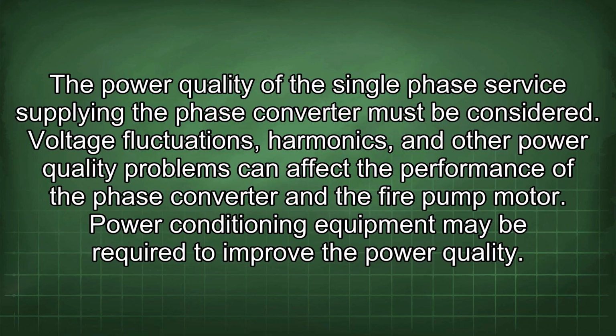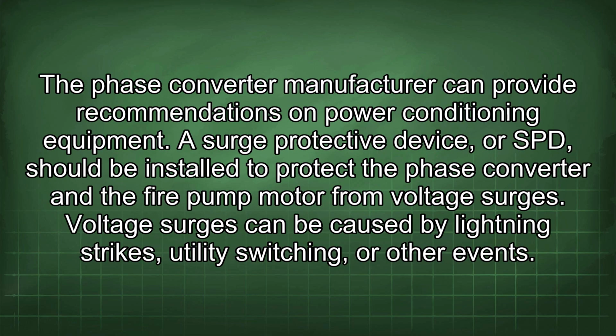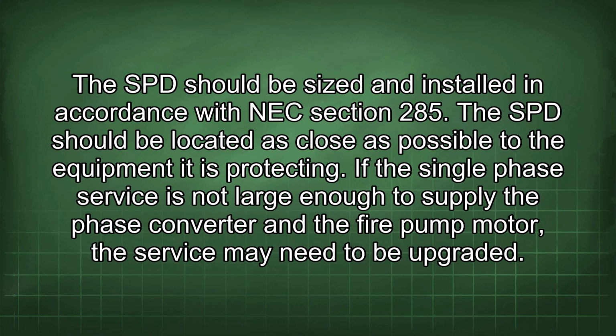The power quality of the single-phase service supplying the phase converter must be considered. Voltage fluctuations, harmonics, and other power quality problems can affect the performance of the phase converter and the fire pump motor. Power conditioning equipment may be required to improve the power quality. The phase converter manufacturer can provide recommendations on power conditioning equipment. A surge protective device, or SPD, should be installed to protect the phase converter and the fire pump motor from voltage surges. Voltage surges can be caused by lightning strikes, utility switching, or other events. The SPD should be sized and installed in accordance with NEC Section 285. The SPD should be located as close as possible to the equipment it is protecting.